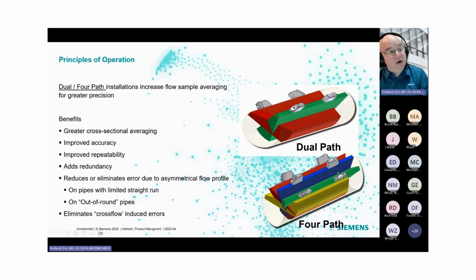And it's interesting to note that on a clamp-on ultrasonic meter, if you were to lose a channel or just a transducer, the meter continues to work with just about the same accuracy. We've had animals break these off. We've had vehicles knock them off, and you just lose a path, but the other paths take over and they just average it out. But again, the reason for the multi-path is just to get more information out of the pipe.